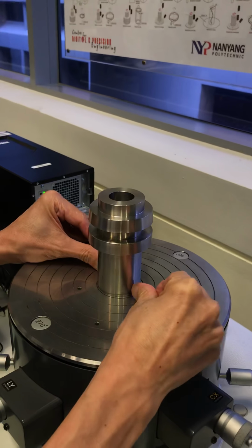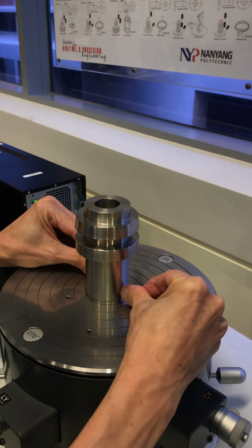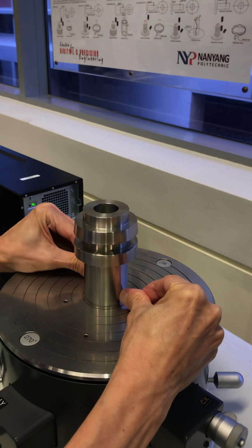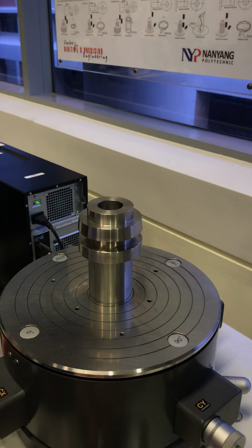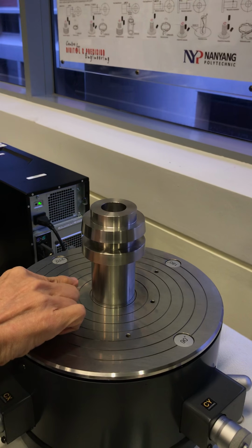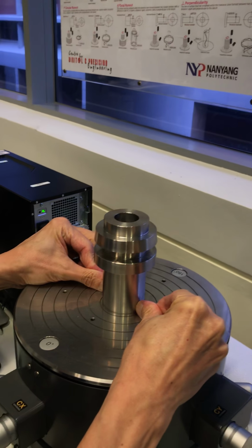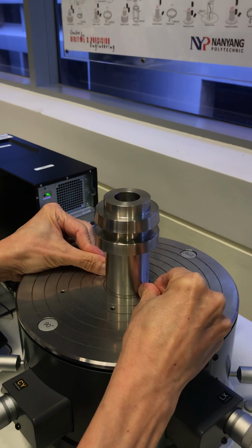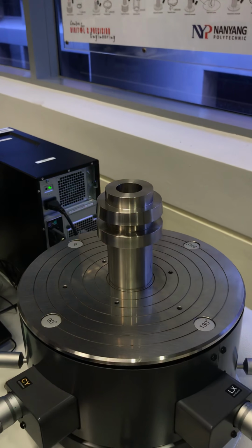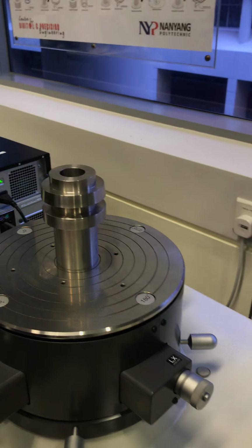Not equal. So just along the axis, 0 to 180 degrees, make sure it is set at equal distance. Then 90 and 270 degrees, you see it is equal? No? And then you repeat. Okay, fine. Any question? Okay, next step is to bring this down.